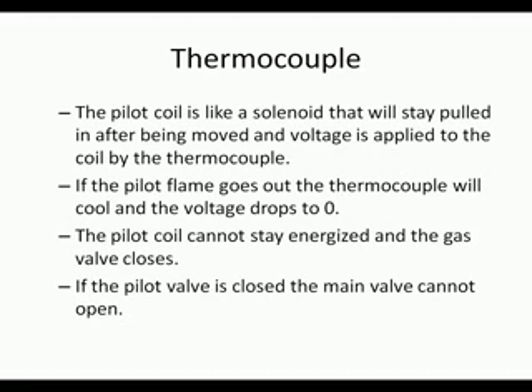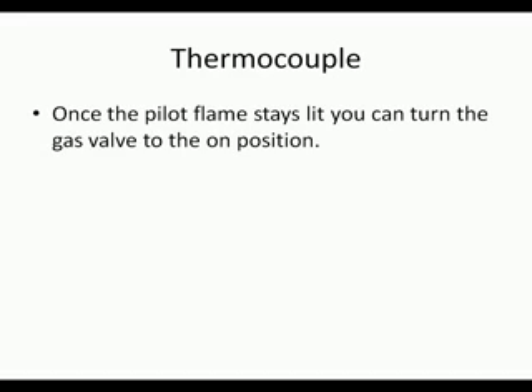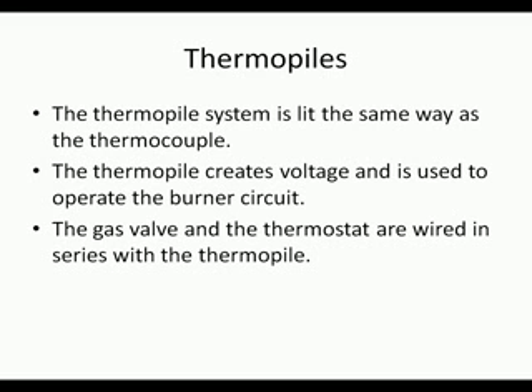The voltage created by the thermocouple is enough to keep the pilot coil energized. The pilot coil is like a solenoid that will stay pulled in after being moved, with the voltage applied to the coil by the thermocouple. If the pilot flame goes out, the thermocouple will cool and the voltage drops very quickly to zero. The pilot coil cannot stay energized and the gas valve will close. If the pilot valve is closed, the main valve cannot open. Once the pilot flame stays lit, you can turn the gas valve to the on position, allowing the main burner to operate.